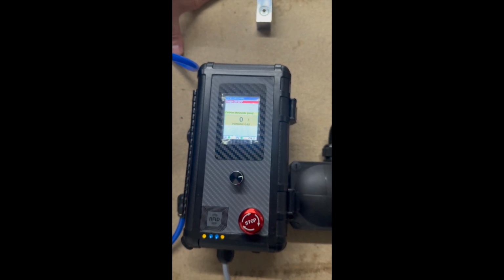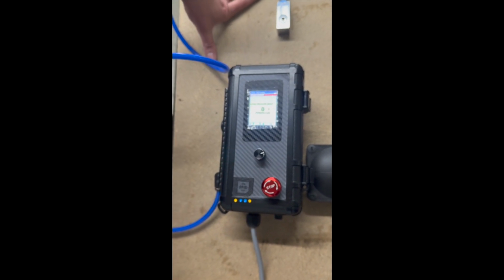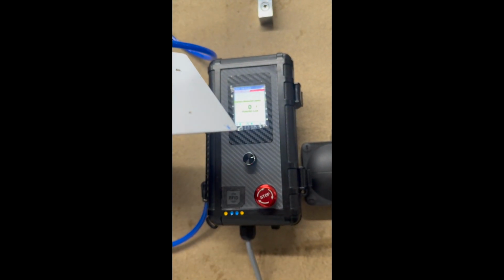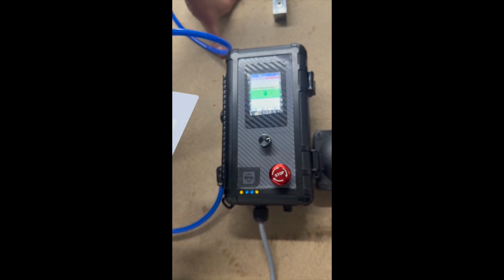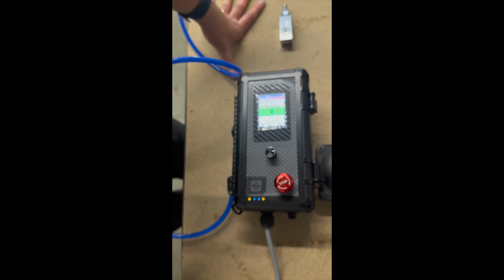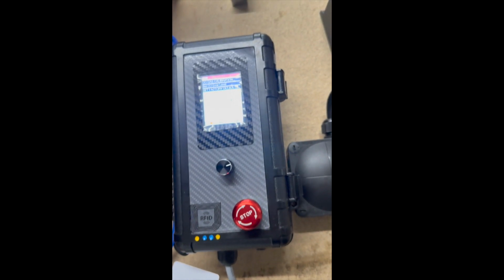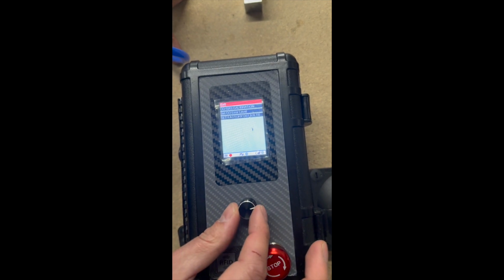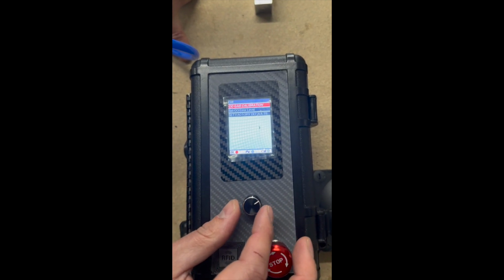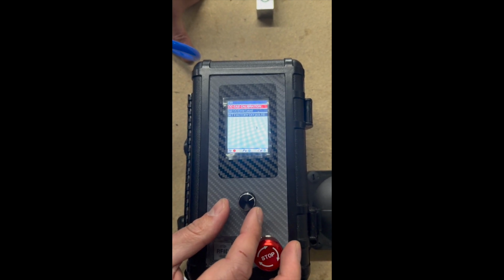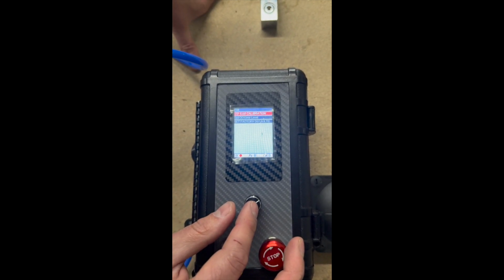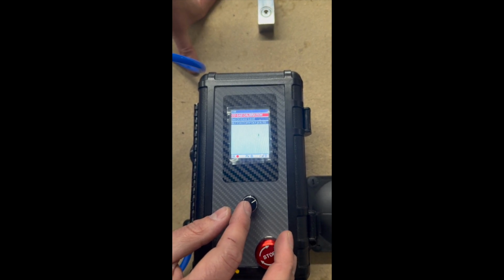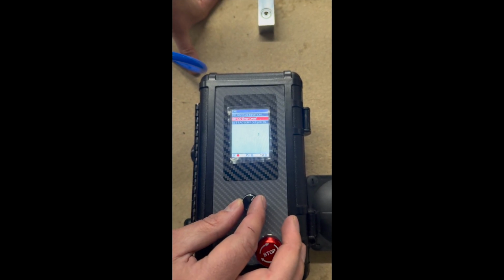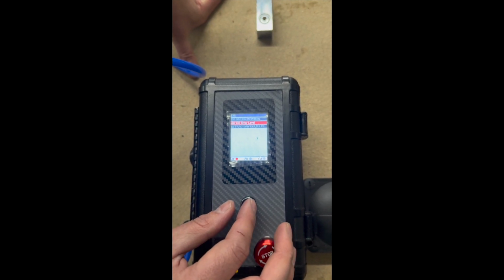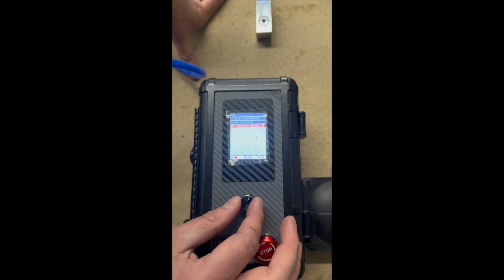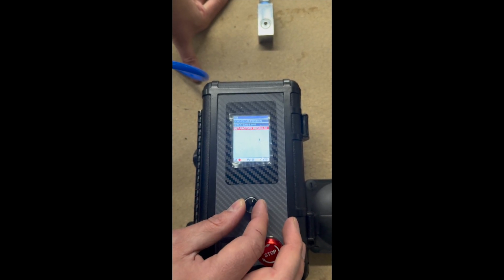We also receive this tool with an RFID card. This RFID card is, if you need to change any settings on the unit, you have to use this MasterCard. Basically, you scan it right here. It goes to the menu. So on the menu, you have one here, CO gas calibration. Whenever you want to do the calibration, you will use this screen, and we recommend once a year. And we have set CO error levels. If you want to change the error level of the CO, you change from this screen. And if you want to set the unit to factory defaults, this is where you do it.